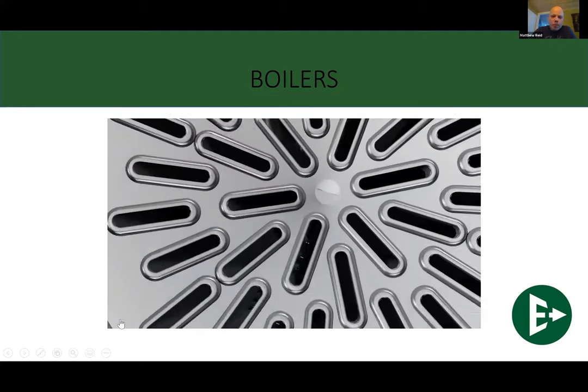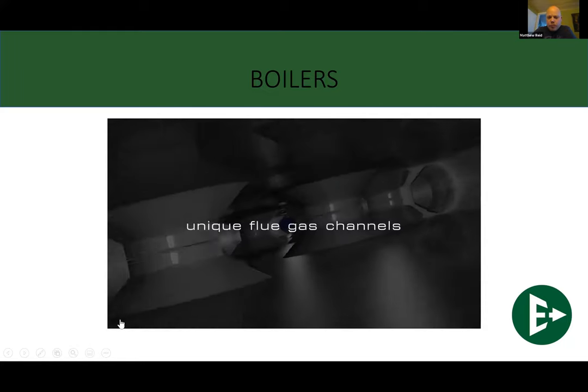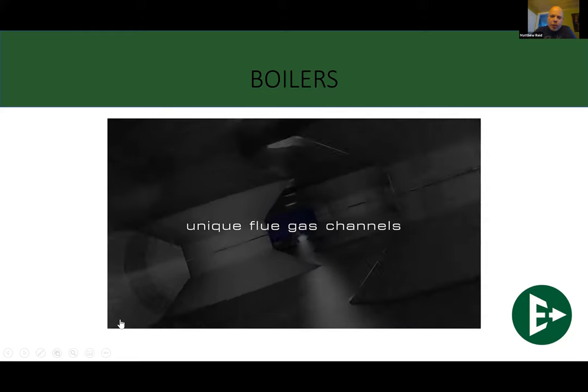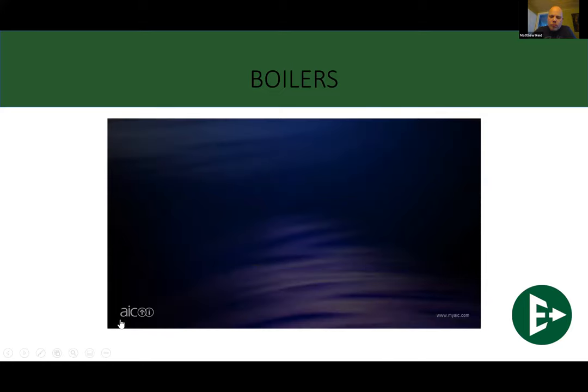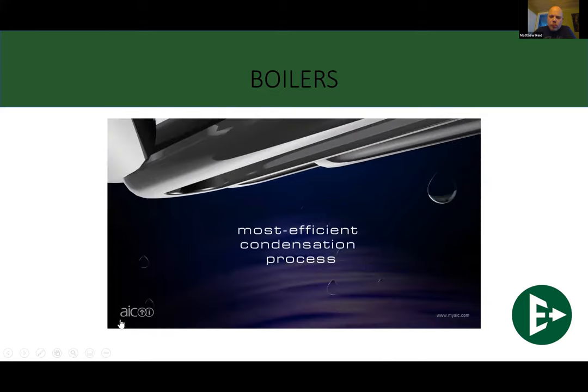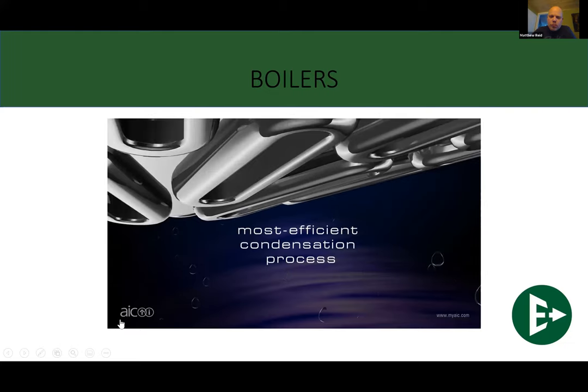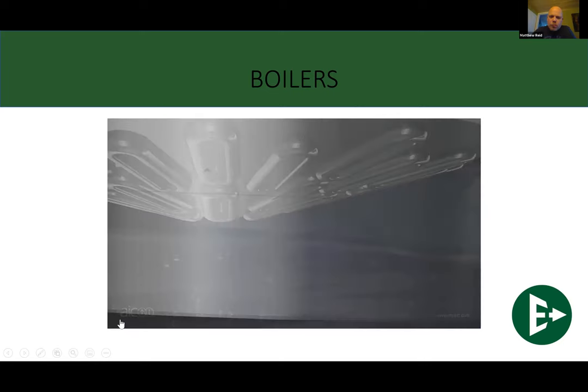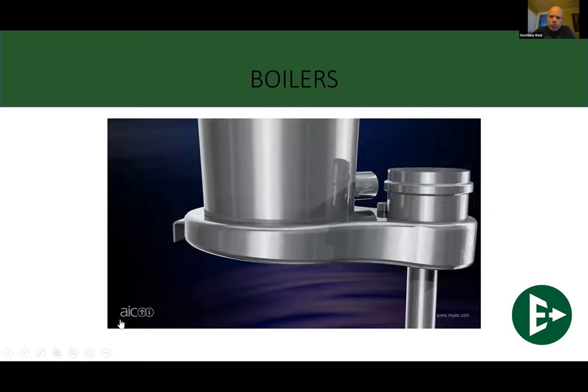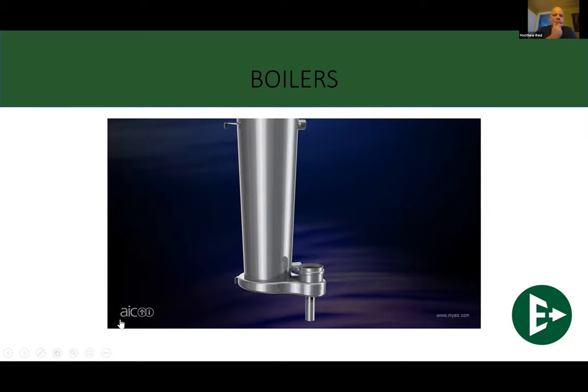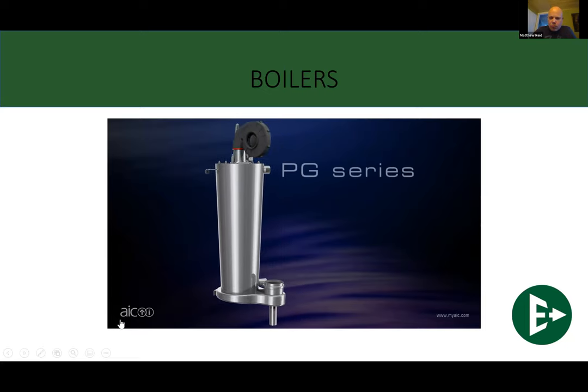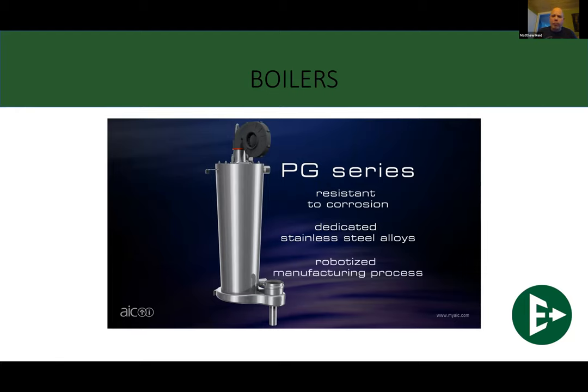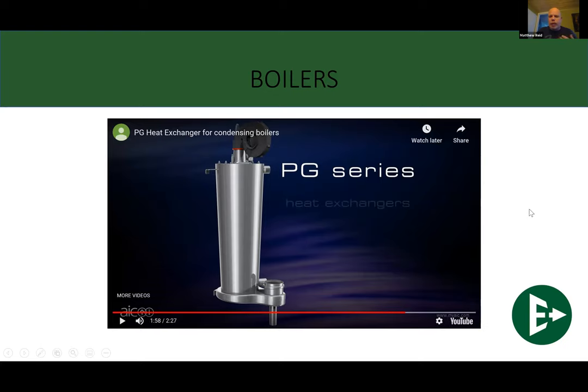Now here we're going down through one of the fire tubes. These are the things that need to be cleaned out without question. With very fine brushes, you can get in there and get a decent clean on these. And that's kind of the overview of how that heat exchanger all goes together and works. The down-fire burner goes through the fire tube, and water comes into the bottom and up, making it super effective at making it sweat as it works.